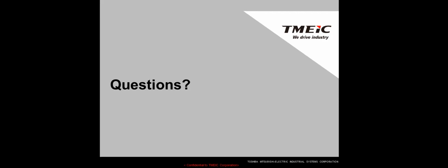Okay, is there a specific software program available for design, settings, and troubleshooting? That's an interesting question. If I understand it, I don't know of any software program that lets you design the drive just via a program that asks you questions. In low voltage drives, a lot of times they're standardized and on the shelf. You say, I want this drive, and it's got this overcurrent rating for a minute and so on, and then you look at the model numbers.